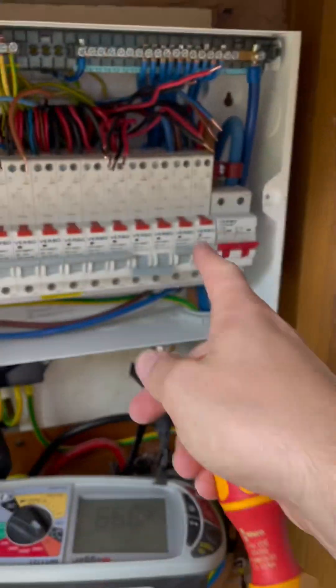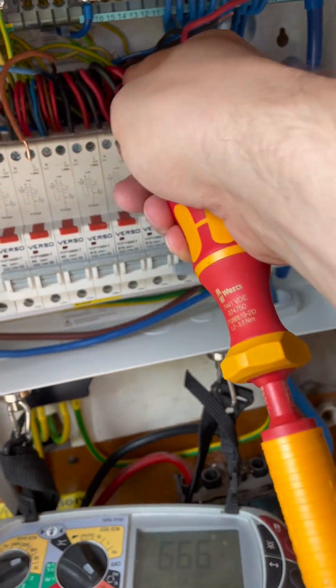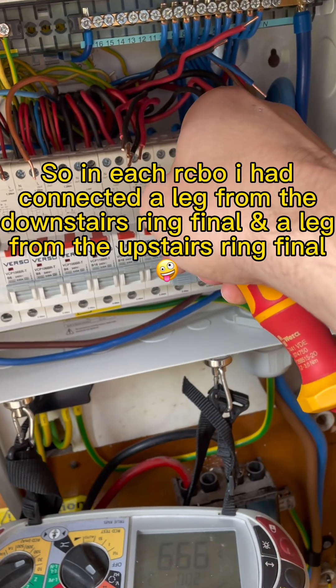None of those are perfect. I made the error of not quite getting the right legs of the ring as I was dropping all the circuits in - I obviously didn't get them right and got them around the wrong way. When I went to turn them on, they just both tripped out. So I stripped them all out.